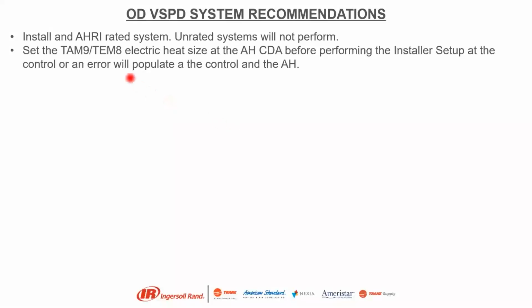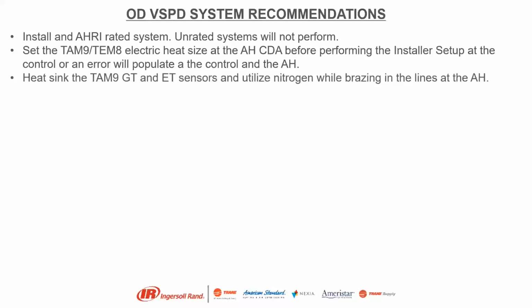You're going to set the TAM9, TEM8 electric heat size at the air handler CDA before performing the test, or else you'll get that configuration fault. So you always want to set those electric heat sizes first thing you do as soon as you power up.